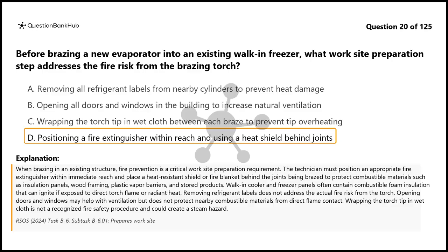Walk-in cooler and freezer panels often contain combustible foam insulation that can ignite if exposed to direct torch flame or radiant heat. Removing refrigerant labels does not address the actual fire risk from the torch. Opening doors and windows may help with ventilation but does not protect nearby combustible materials from direct flame contact. Wrapping the torch tip in wet cloth is not a recognized fire safety procedure and could create a steam hazard.